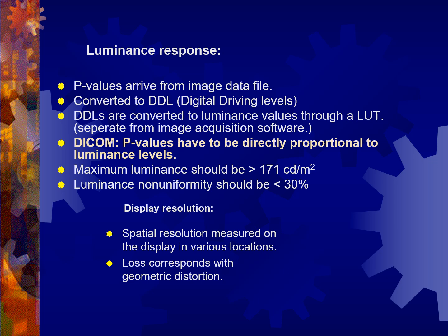You measure the luminance and check to make sure the measurements at all locations on the monitor are basically the same. If there's a greater than 30% difference, when the pattern is supposed to display the exact same color throughout, then you have a bad section of the monitor.